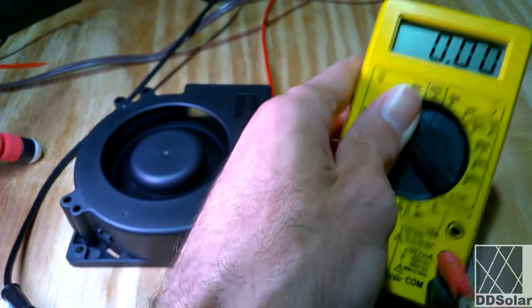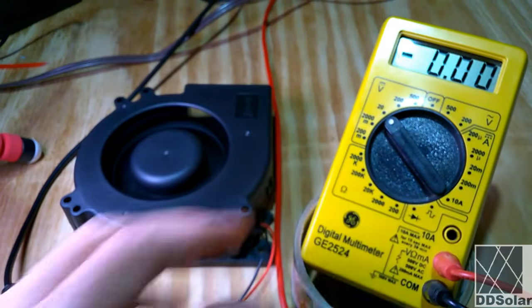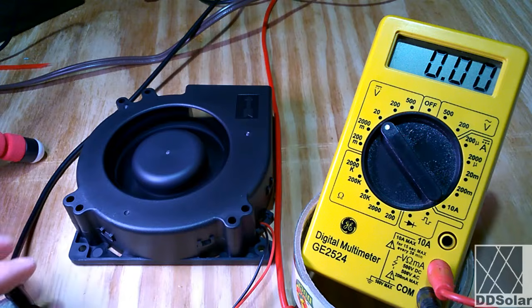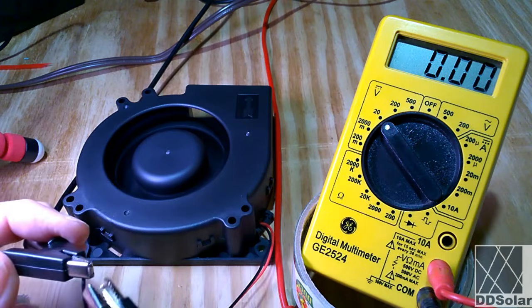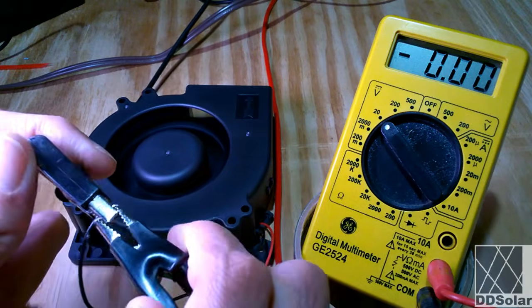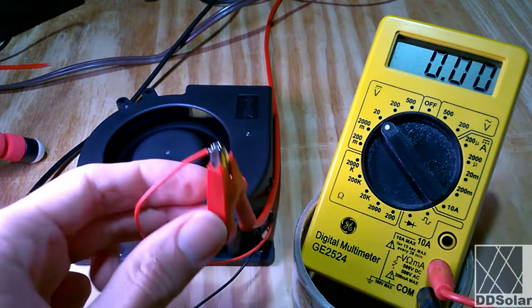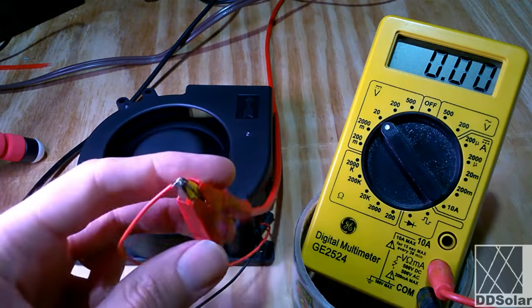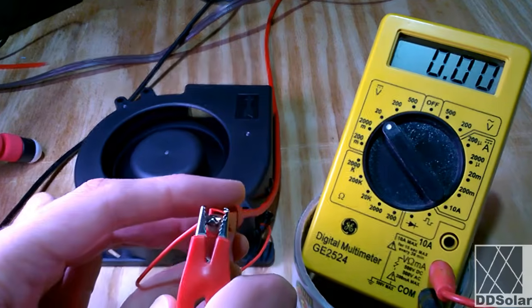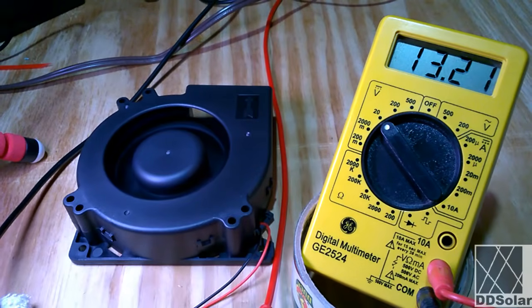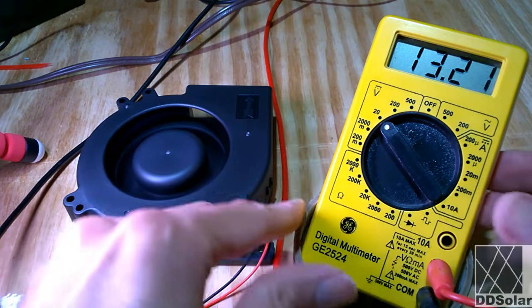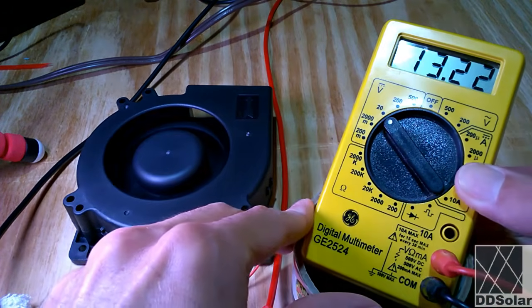Now I'm going to take the measurement of the battery or the power supply or whatever it is while it's in operation. So in order to do that, I simply take the power connection for the negative, and I'm going to attach my meter to that. Then I'm going to take the positive side right here, which is feeding power to the fan also, and I'm going to attach my meter to that side. And you can see that the loaded voltage present at the terminals of the fan is 13.22 volts, or 21 volts. It's jumping around a little bit, and that's perfectly normal, and it's nothing to be alarmed about.